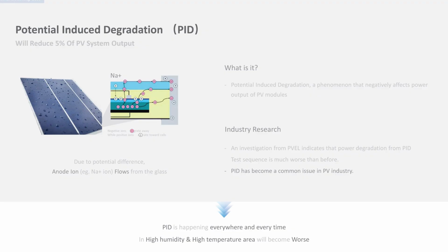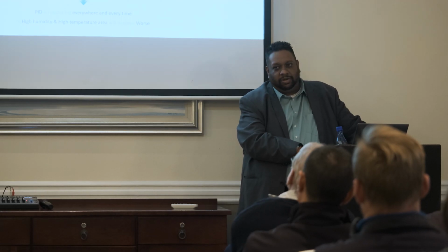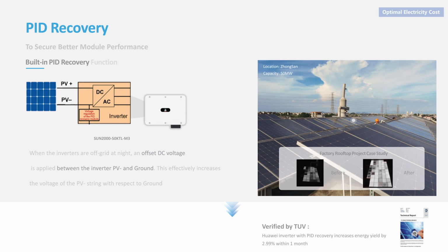Okay. PID. Anyone knows what's PID? Yeah. So it's called potential induced degradation. So it's a phenomenon that solar panels suffer from because of the aluminum framing. So the aluminum framing together with the glass allows positive ions to interact with the substrate, okay? And that causes degradation. You would only notice it after time. If you do some infrared photographs of the panels, you'll see that there's some degradation in the panels itself. So we have on the inverters from 50 kilowatts and below, we have anti-PID built in, okay? So let me tell you what anti-PID does, okay? So the PID recovery that we have, that function, what it does is that at night, we will offset that positive ions by sending a negative voltage to the panels.